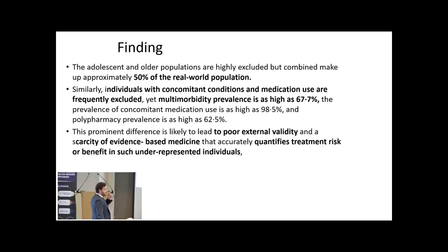So the lesson learned from this is that when you want to get sufficient clinical data, you need to get it from different designs. Not only one design, but from different designs. You need a restrictive design when you want to provide a high quality level of evidence. I'm speaking here for high-risk devices, obviously. And you need to combine that with information from the vulnerable population you excluded at first. Then you will get a representative population, and you will know the real impact of your device in the real-world setting.